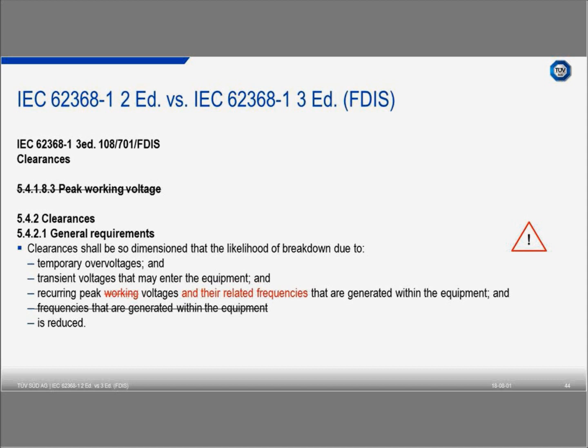Another topic is the list for clearance. Previously there was a listing of temporary overvoltages, transient voltage, recurrent peak voltage, and frequencies generated in the equipment. Now there's a clarification: we have to check the recurring peak voltage and the related frequencies carefully. If there's recurrent peak voltage at different frequencies, we have to measure all of them and take into account which has the highest influence on the clearance in this area. That's the change here.